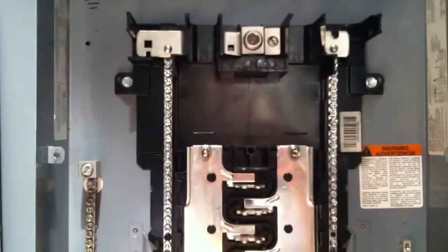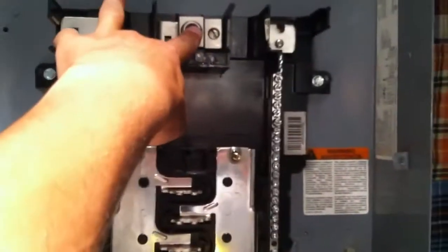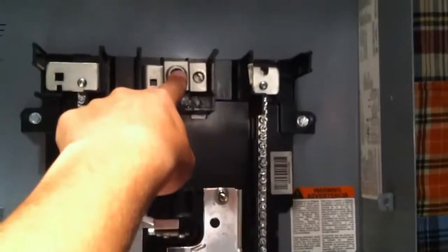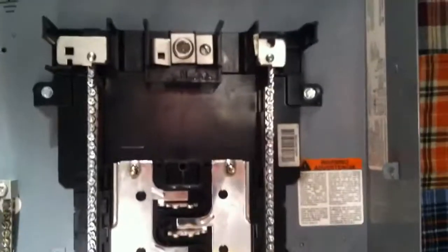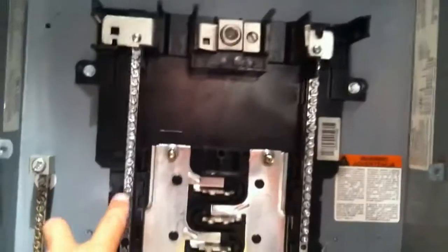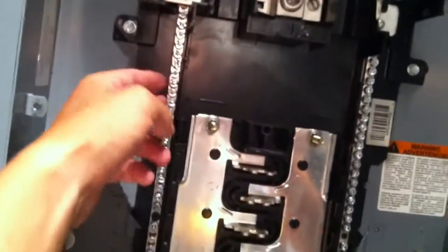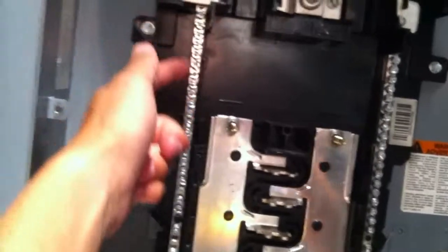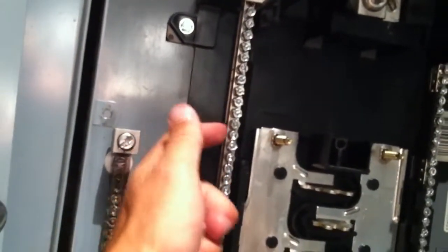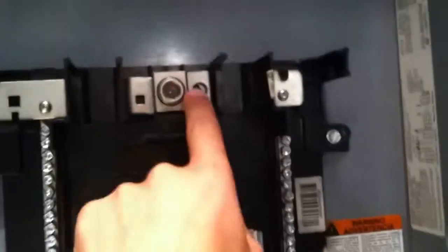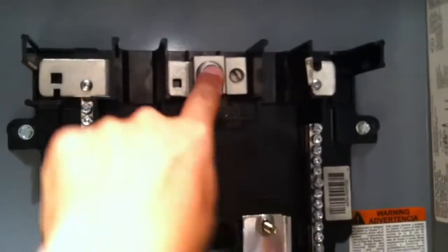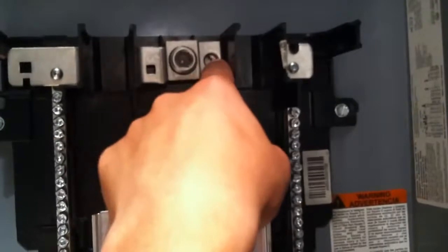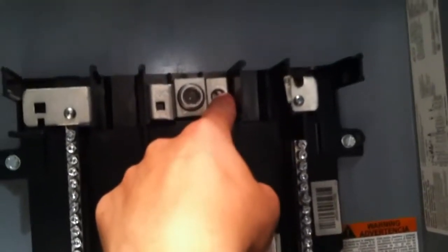But here in California, in the United States, where I am, in the main panel that comes into your house, where your main feed comes in, your ground and your neutrals are on the same bus bar. So they are the exact same wires. They're actually bonded together on the same little terminal strip here. So your ground wires and your neutral wires will both go to this strip. Okay, and then this huge thing is for your neutral wire. This is for your ground wire there. Okay, that's if this is a main panel.